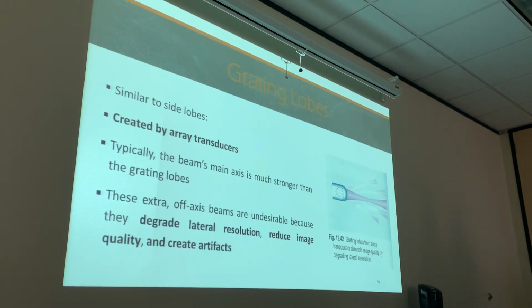Grating lobes, which are similar to side lobes, are created by array transducers. Transducers with multiple elements, right? Typically, again, the main axis of the sound beam is much stronger than the grating lobes. You can see they're kind of faded. They're really weak. Yet and still, those sound beams travel into the body, reflect off the body, come back to our transducer and create degraded lateral resolution, reduce image quality, and they create artifacts. They create noise. They're actually decreasing our signal to noise ratio. We want our signal to noise ratio to be increased. We want our signal to be high, our noise to be low. When you decrease the signal to noise ratio, you bring them closer, right? Now we have just as much good signal as we have noise. We don't like that.